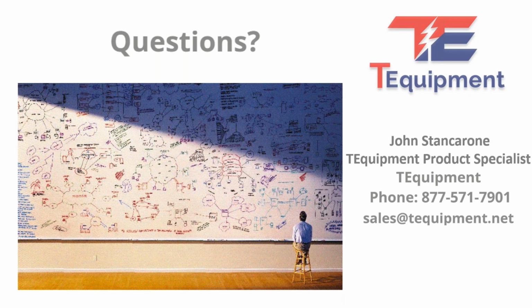So standards, unfortunately, do not. We are not there with the standards. However, from the slides, I think I mentioned one, but I forgot to mention the other one. So within the string, like interstring measurement, you want to have less than 5 milliohms. And from string to string or from rack to rack, you want to be below 100 milliohms. Those values are values that we have seen from the field and from multiple support calls that we get, and those are the typical values.